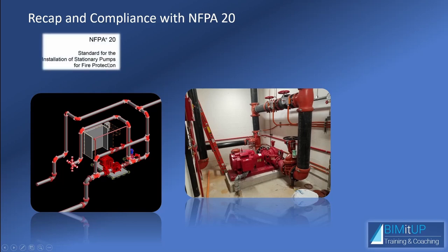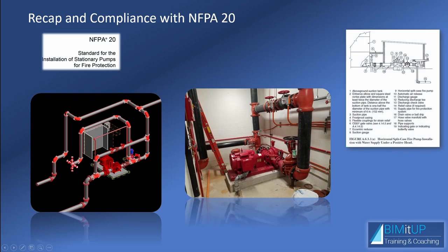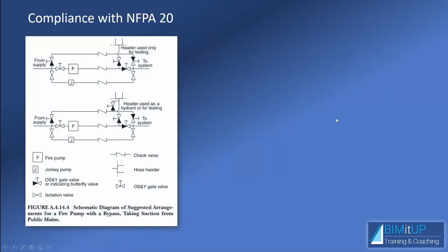So NFPA 20 is the standard for the installation of fire pumps. And they not only describe all the accessories that should be included, but they also propose a couple of layouts. This is suggested, this is not mandatory. For this presentation, we're gonna go with the first layout. The only difference between these two is that in the one on the top, you're using this test header, which is the one that you saw with the fire hose valves. You're using it only for testing. In this one, you can use it for testing.